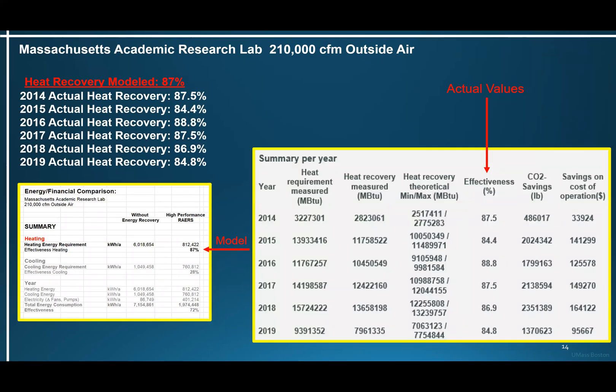Another system — an academic research lab in Massachusetts with 210,000 CFM of outside air. The model calculated 87% annual heating effectiveness. Actual post-occupancy results: 2014 — 87.5%, 2015 — 84.4%, 2016 — 88.8%, 2017 — 87.5%, 2018 — 86.9%, and 2019 — 84.8%. Again, pretty close to the model.